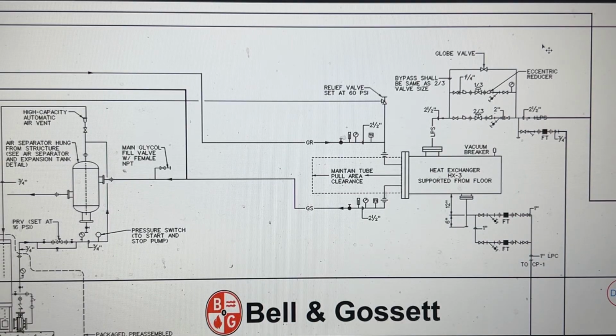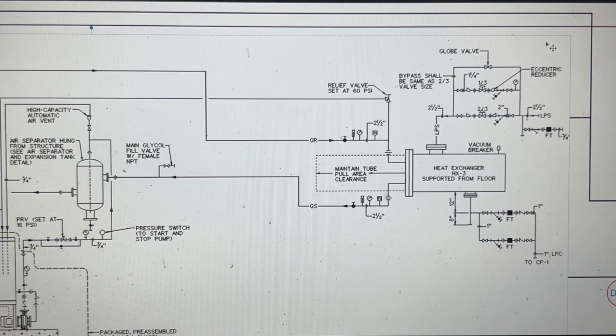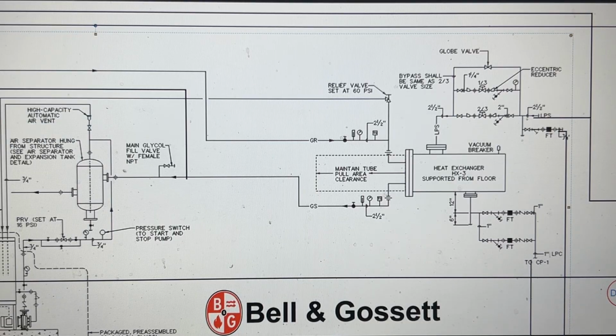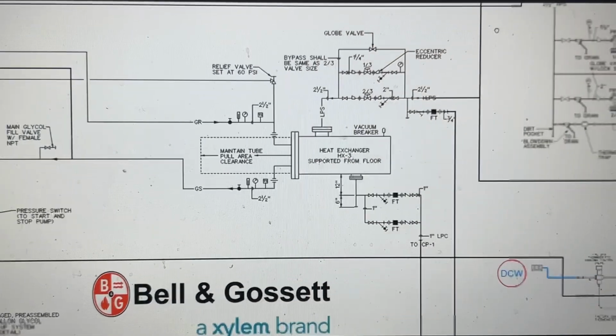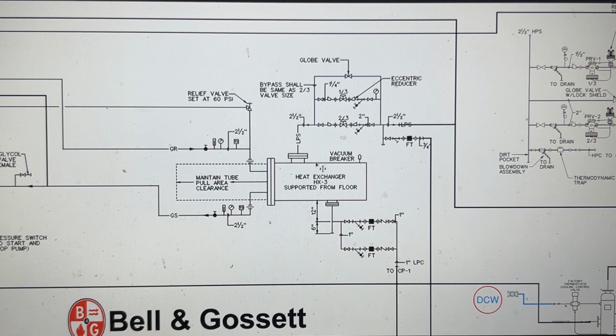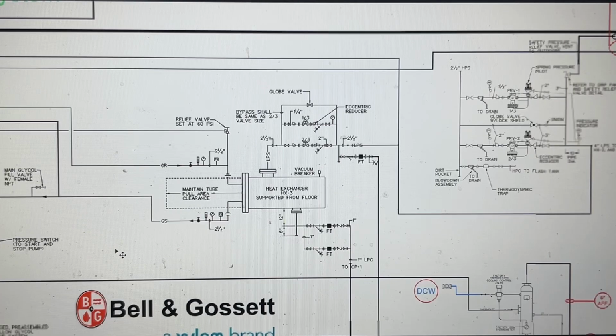Let me zoom in on this. I keep doing that. So we got steam coming into the heat exchanger, 1/3, 2/3 control valves based on demand. It goes through the coil here and heats up that glycol going through the coil of the heat exchanger. Obviously condensate out. So glycol supply and return, cruise there. That's where it picks up the heat to take it up to the roof to that coil.